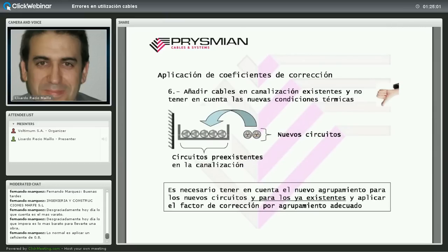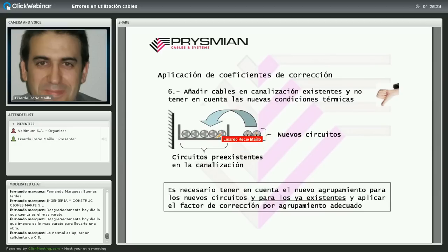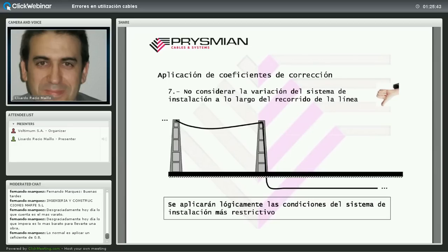Otro error frecuente: tener una instalación preexistente e instalar nuevos circuitos en la bandeja existente de la forma más cómoda, olvidando los coeficientes de corrección por agrupamiento. Al añadir nuevos circuitos se dificulta la disipación térmica. Habría que recalcular los circuitos existentes junto con los nuevos. Quien haga esto está cometiendo un error, ya que altera las circunstancias en las que se instalaron los cables originales.